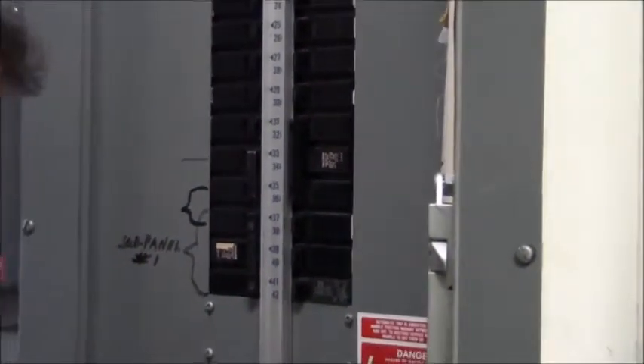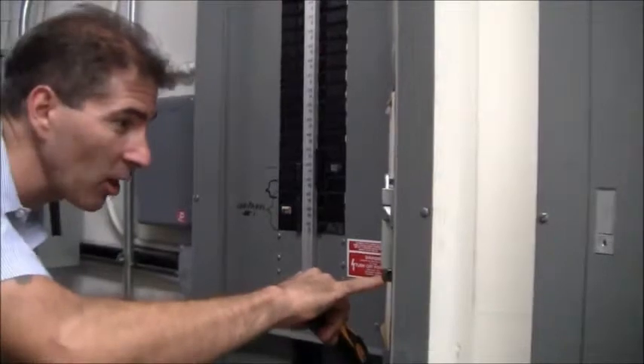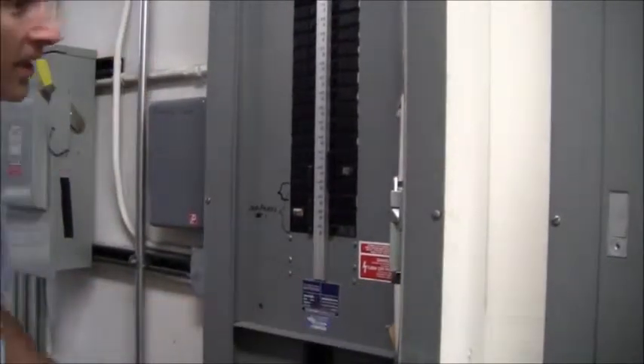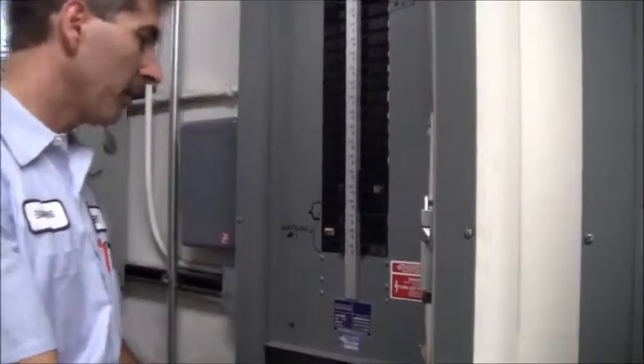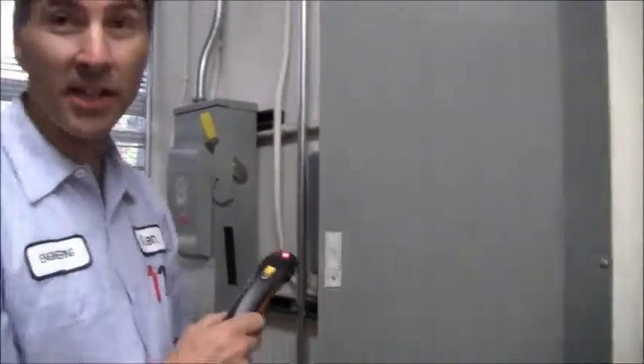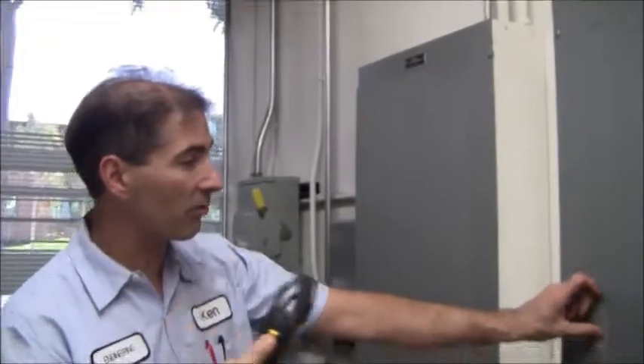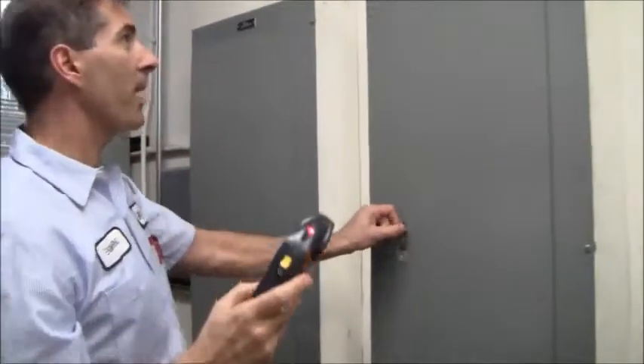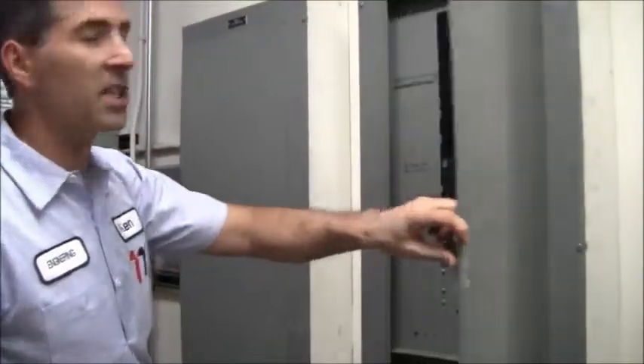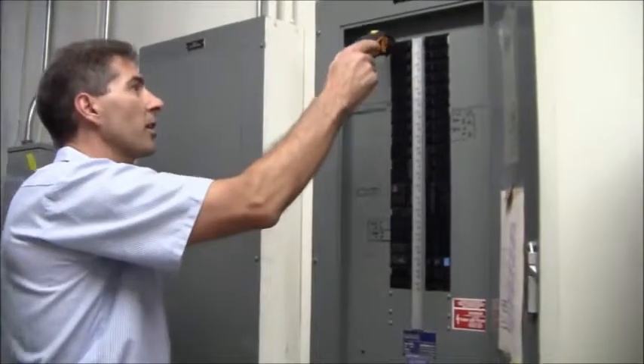There's a legend here, and breaker 40 says that it's going to a computer. So before I do any testing on breaker 40, I'm going to shut this off, which will reset it, turn it back on, and strike this panel again to see if anything comes up, starting with the left.